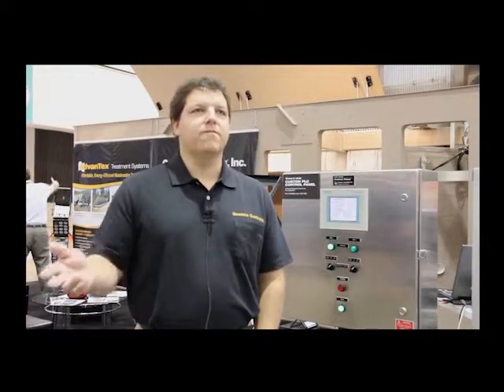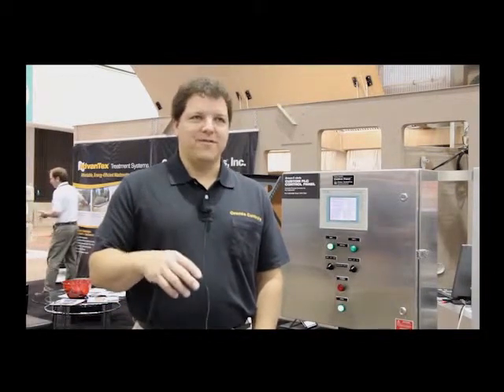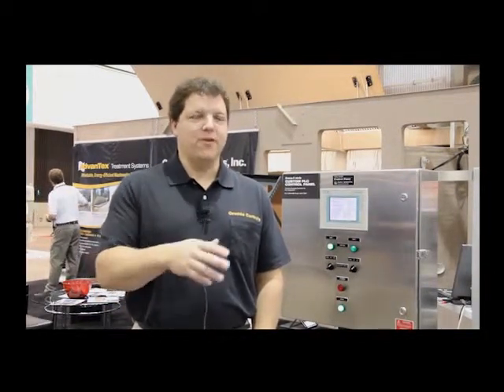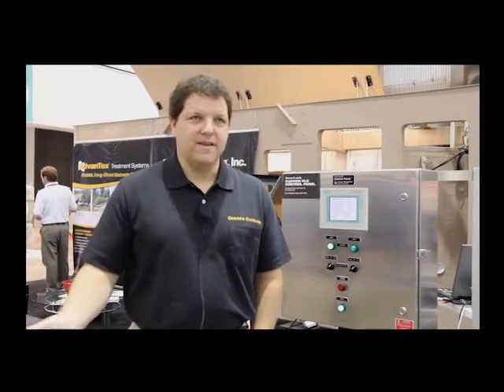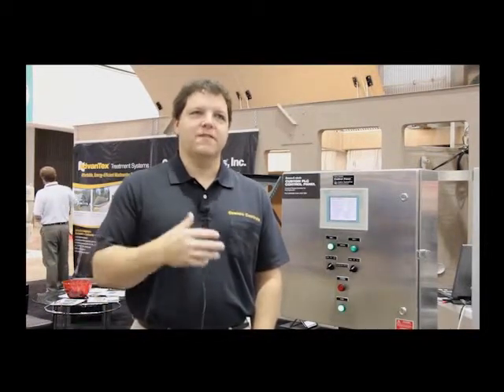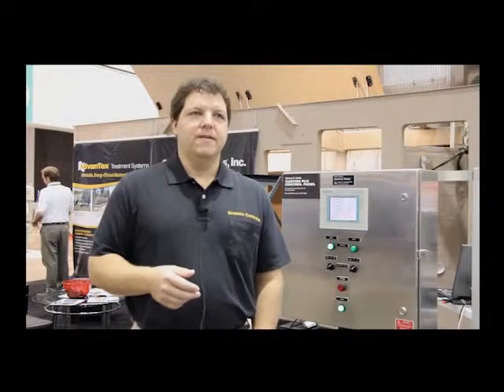The main considerations are how do you want to start the motor, how do you want it to run, and then environmental concerns, where the location is. The environmental concerns would be: where is this panel located? Is it indoor or outdoor? What type rating does it need to have? How hot does the ambient temperature typically get, and how cold does it get? All of those considerations will extend the life of the control panel if you approach it correctly.